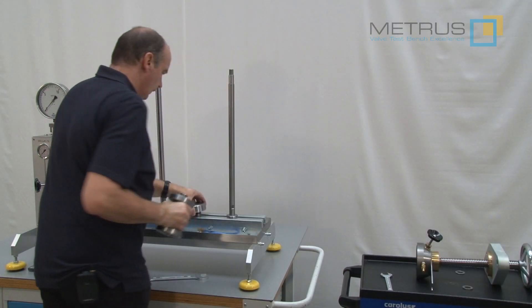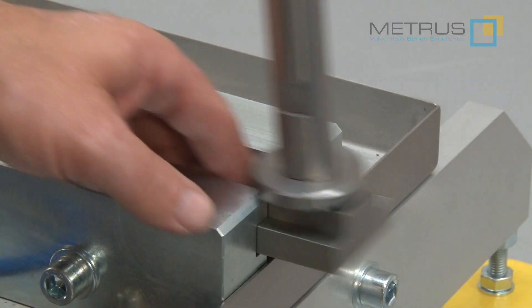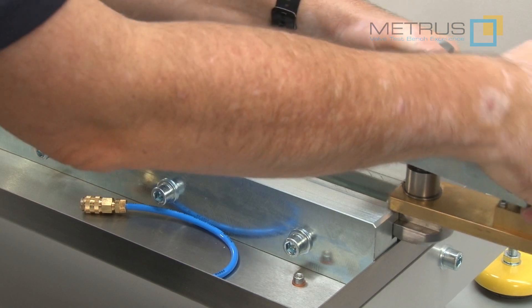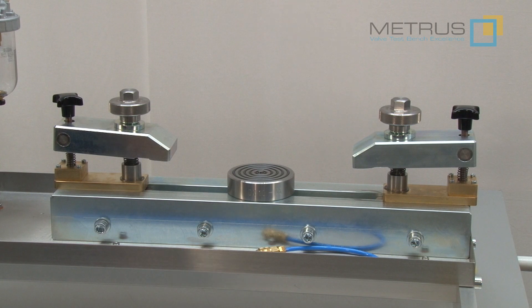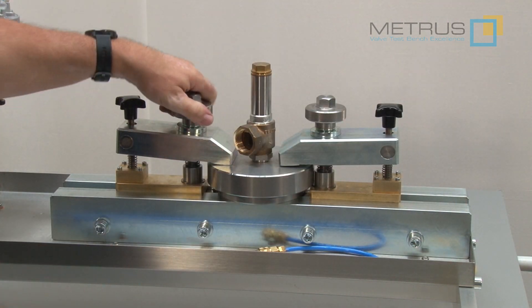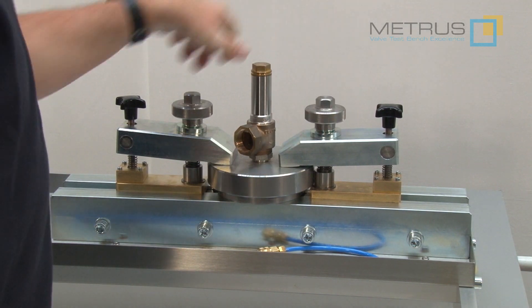Simply loosen the nuts, lift the head beam, remove the distance piece, untighten the distance bolts and remove them. Now you can replace your standard clamping jaws. For threaded valve ends you can also use our threaded adapters, which are available in NPT or BSP threads, male or female threads.